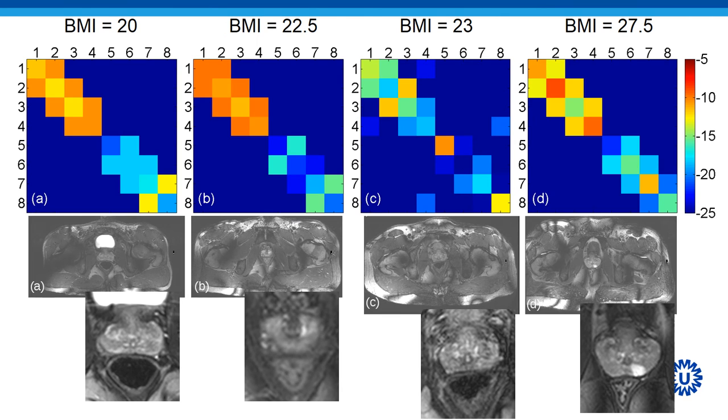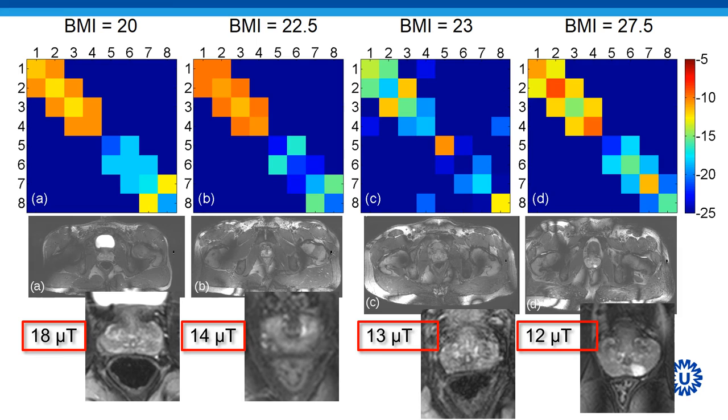If you look at the image quality, it's not that superior because the fat suppression pulse didn't work correctly. But if you look at the B1 plus values, you can see that we were able to reach 12 microtesla for subjects with a BMI of 27.5, up to 18 microtesla for subjects with a BMI of only 20.